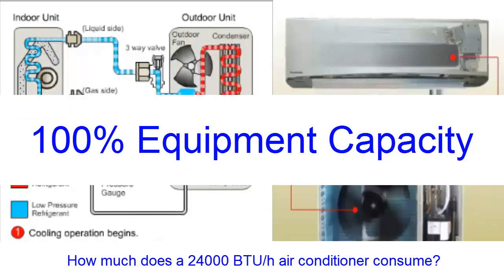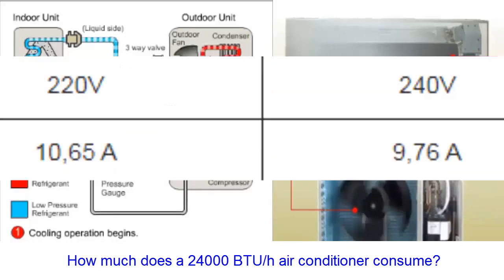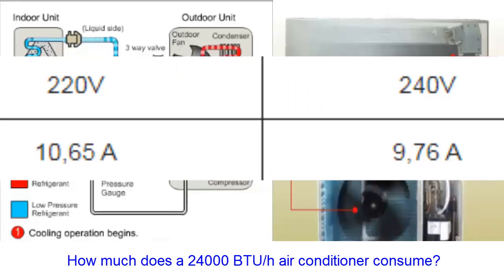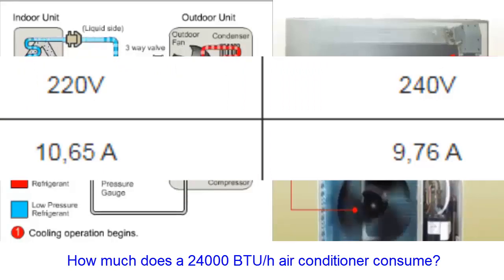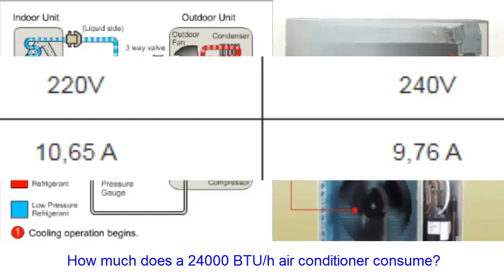For a single phase power supply voltage of 220 volts, the average current consumption of the equipment at 100% capacity is 10.65 amperes. For a single phase power supply voltage of 240 volts, the average current consumption at 100% capacity is 9.76 amperes.